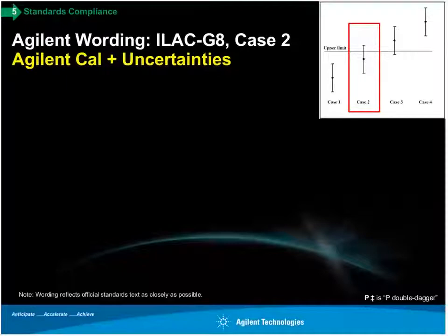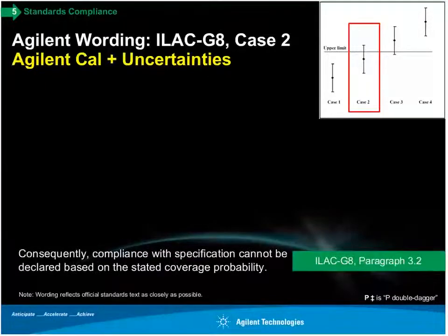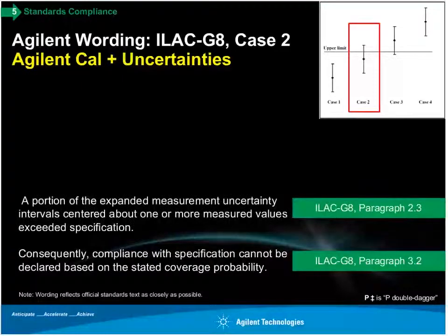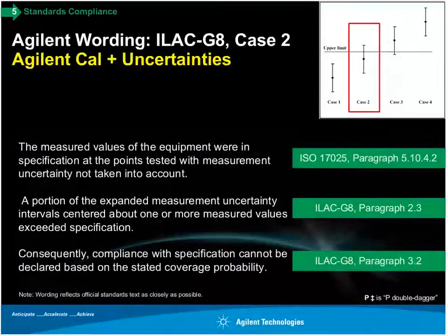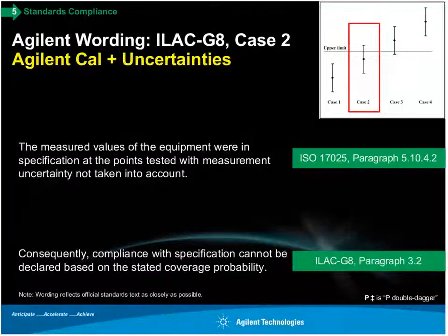Here's what we've done at Agilent. One of our services is called Agilent Cal plus Uncertainties, by which we mean the Guide to the Expression of Uncertainty in Measurement. For case 2, we designate that as a pass with the double dagger symbol associated with it. What that means, the P double dagger or pass double dagger, you can see in the words here on the left. We've written the words that you will see in our measurement report to correspond as closely as possible, if not exactly, to the various paragraphs in 17025 or ILAC G8. So that's the case where you measure a point that is just inside.